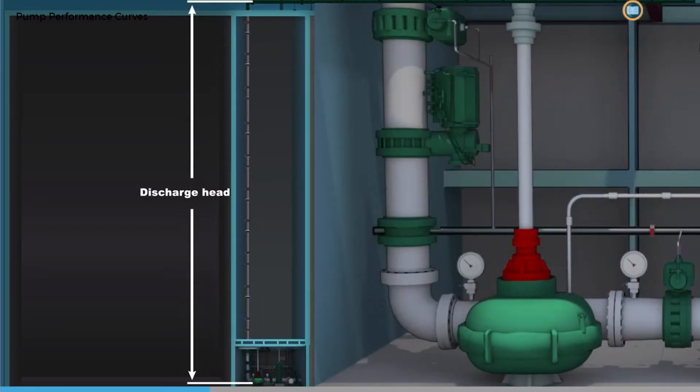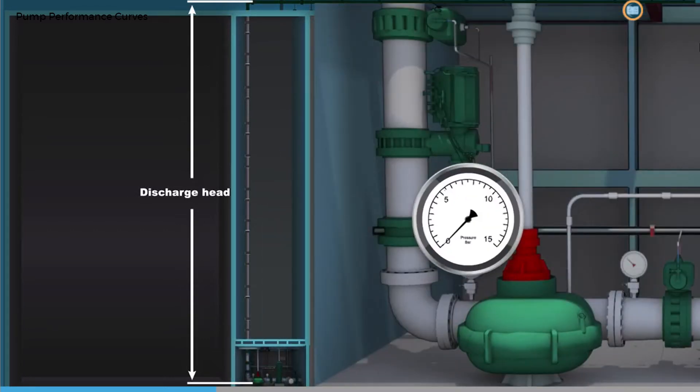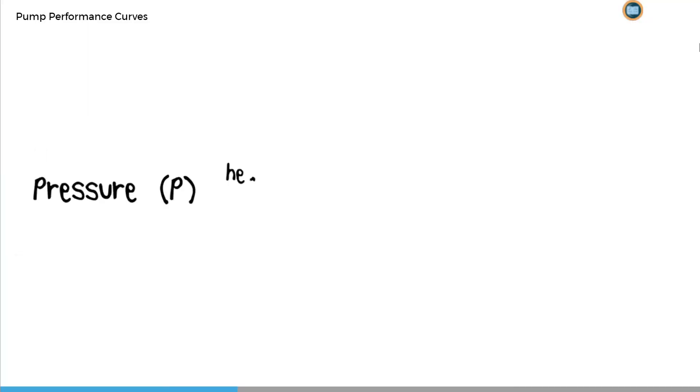This is usually measured in meters, but can be converted to the more familiar unit of pressure known as bar. We do this by multiplying the head by the density of the liquid being pumped, and dividing it by 10,197.